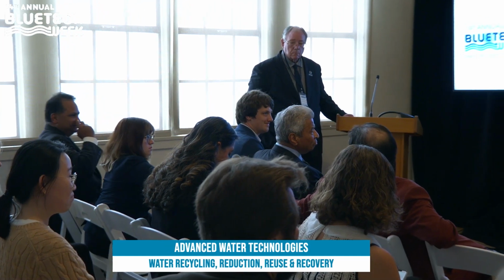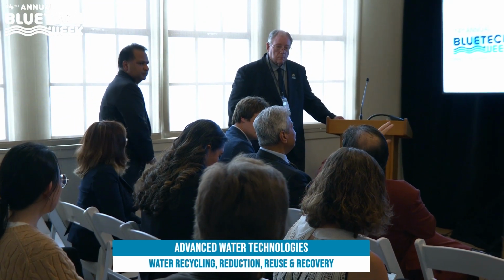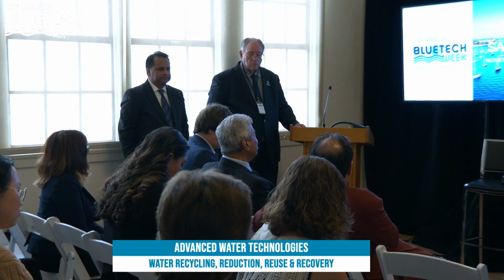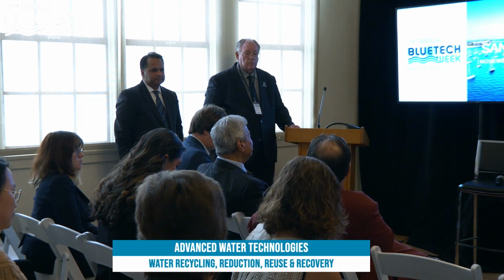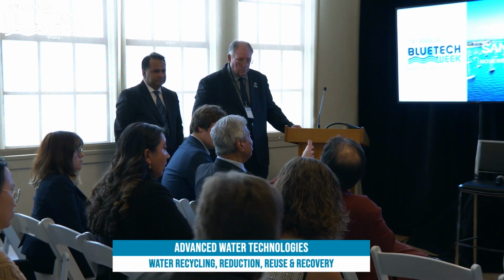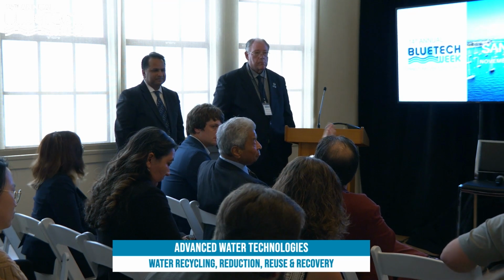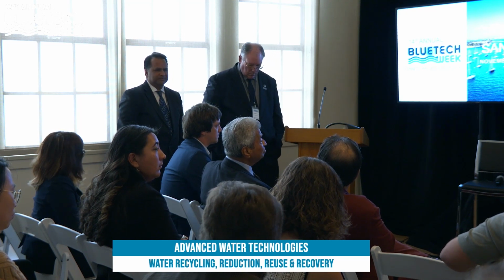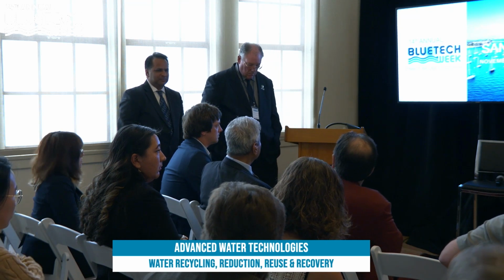I highly agree that the whole system contributes. For the past couple of years, I've been an integral part of brine management with our mutual client back in Saudi Arabia. One of the issues that I've always been having is high temperature, for two reasons. The water is at a higher temperature over there than other places. And the second is that by the time it passes all of these high pressure pumps and you're looking at several stages, it gets much hotter, 50 degrees centigrade or whatever. And that kills the performance, flux and rejection of the membrane all along. In your new product, how are you mitigating for that impact?